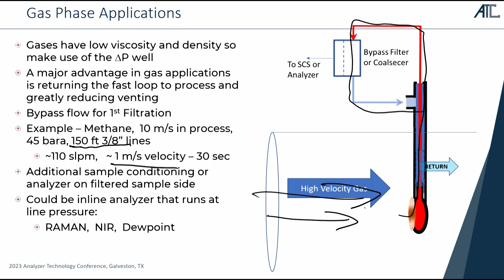This goes completely against everything I've ever taught all of you in a sample conditioning class, where I've said, if you've got a high pressure gas, the first thing you want to do is put a regulator in to lower the pressure. We're actually saying we're going to build this fast loop at high pressure. It goes completely against everything we talk about in our sample conditioning classes, where we say if you want fast response time, go with really narrow diameter tubing. This loop will run faster if I put larger diameter tubing in because the tubing contributes less pressure drop then. But it allows me to create a fast loop that will continuously run and return to process.